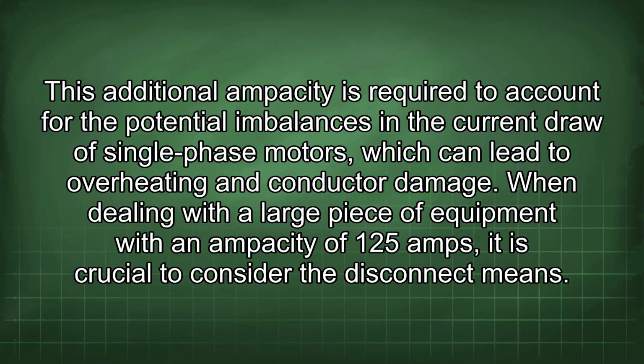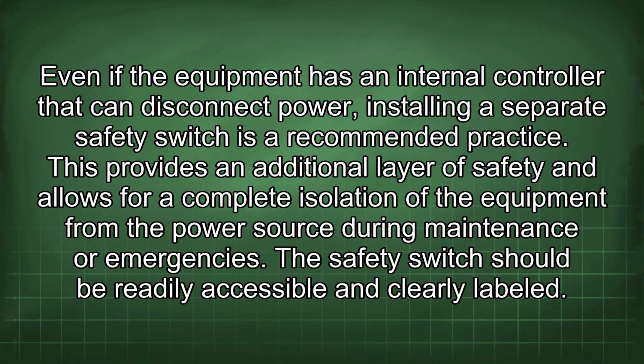When dealing with a large piece of equipment with an ampacity of 125 amps, it is crucial to consider the disconnect means. Even if the equipment has an internal controller that can disconnect power, installing a separate safety switch is a recommended practice. This provides an additional layer of safety and allows for a complete isolation of the equipment from the power source during maintenance or emergencies. The safety switch should be readily accessible and clearly labeled.